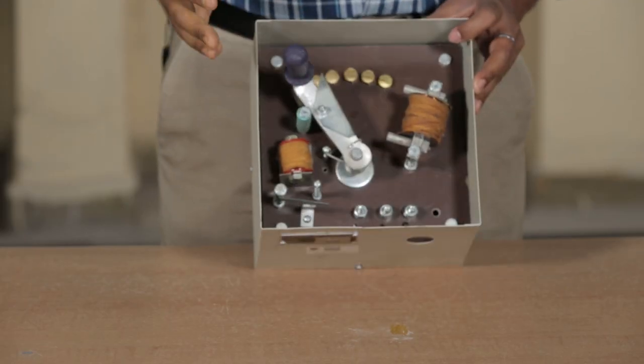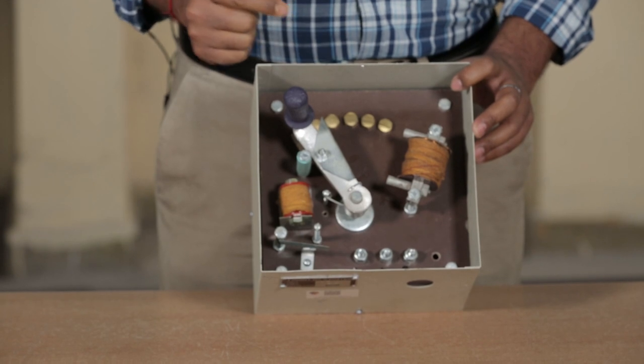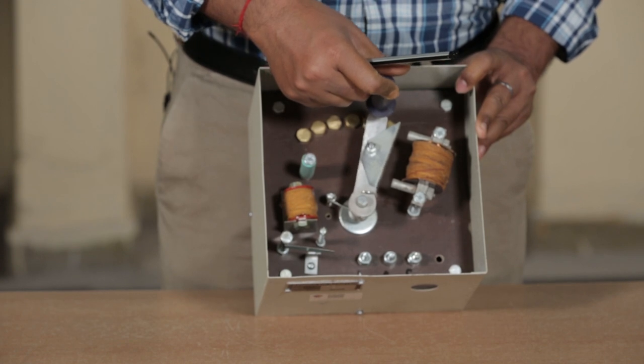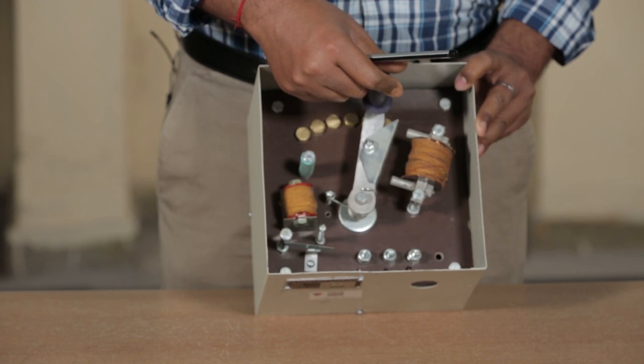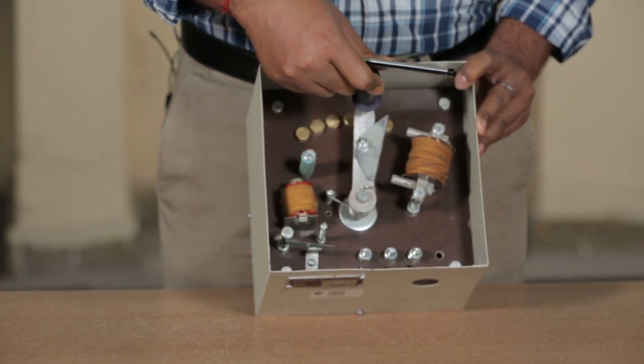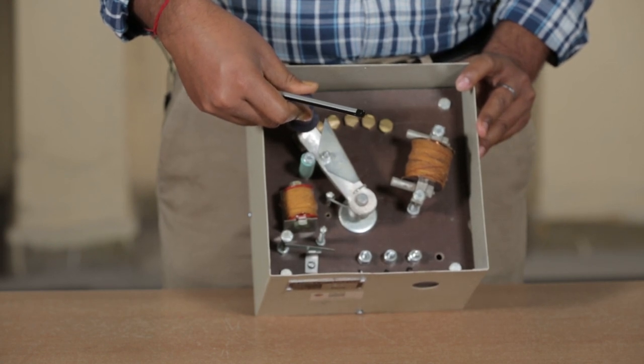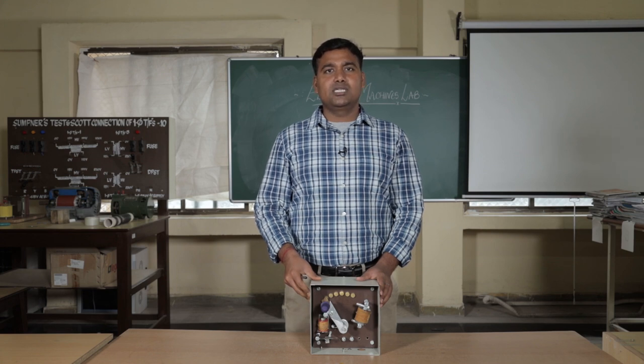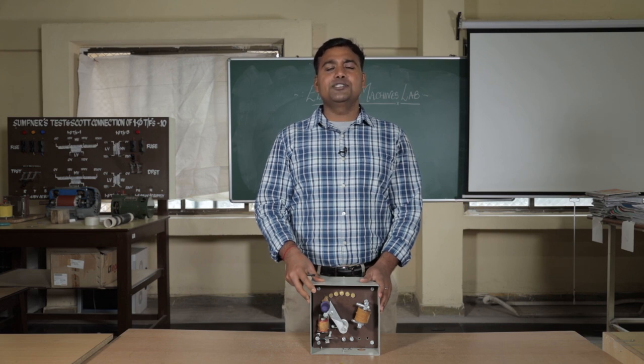This is a 3-point starter, which is used to restrict the initial amount of current by slowly revolving the handle so that resistance is added slowly. On completing the experiment, the handle will automatically come to the minimum point when we turn off the supply. 3-point starters are used for shunt motors and 2-point starters are used for series motors.